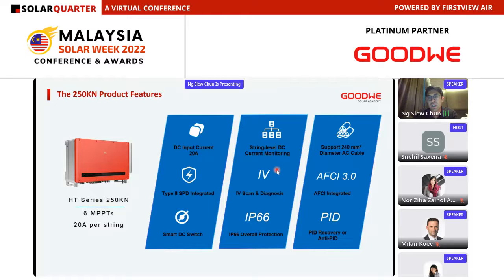And of course, in terms of features, we also support string level DC current monitoring. We support IV scan function to save on the operation and maintenance costs. And also all our inverters are IP66. And in terms of capex investment, we support AC cable in aluminum. We support up to 240 square, so clients can use 240 aluminum cable for cost savings purposes. And we also have optional arc fault circuit interrupter, AFCI functions, as well as PID functions, so anti-PID functions as well. All these are available here.